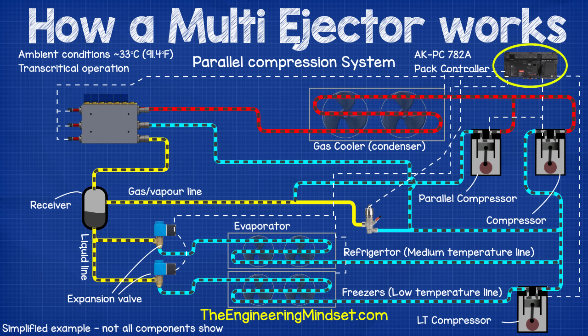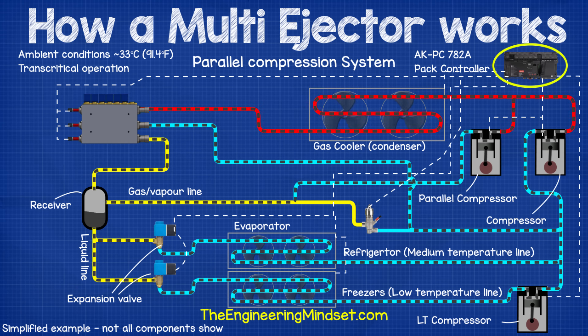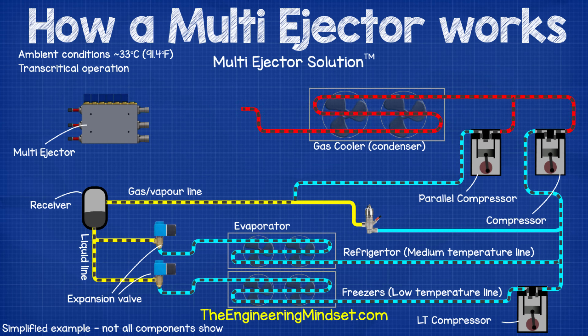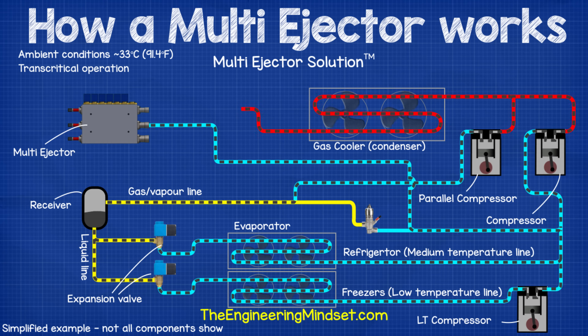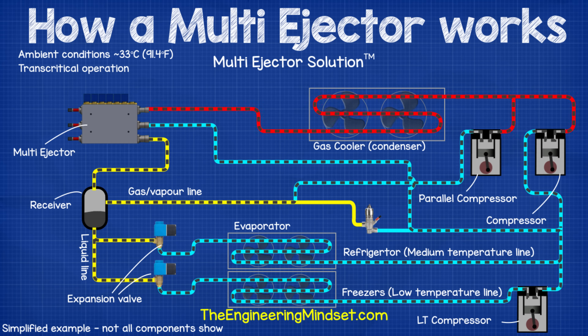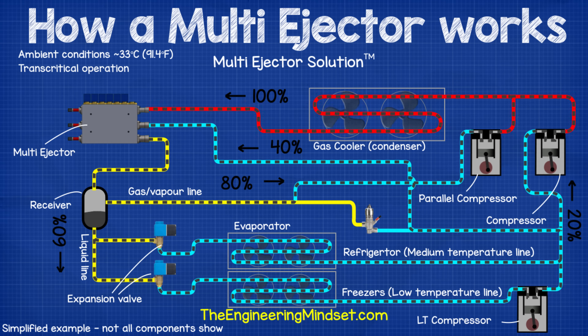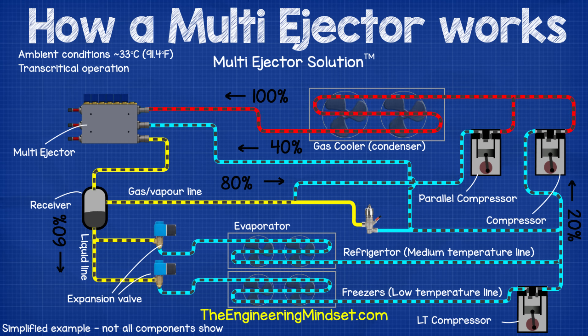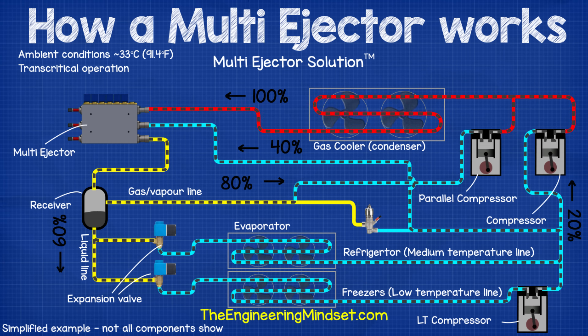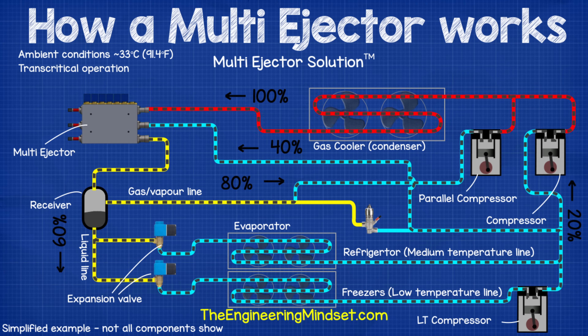The third-generation design — the most energy-efficient CO2 system designed to date — uses the multi-ejector with an AK-PC 782A pack controller. A line runs from the suction line of the main compressor and feeds into the multi-ejector, as does the high-pressure line from the gas cooler. The multi-ejector lifts around 40% of the refrigerant from the suction line, mixes it with the flow from the gas cooler, and feeds it to the receiver. 60% of this mix flows to the evaporator and 80% flows to the parallel compressor, meaning only 20% is compressed by the hardest-working main compressor.